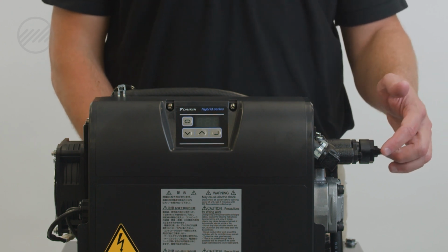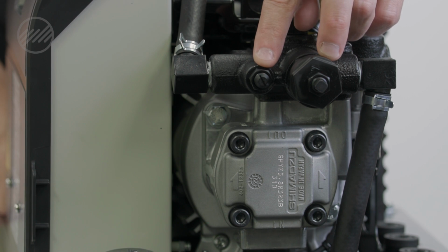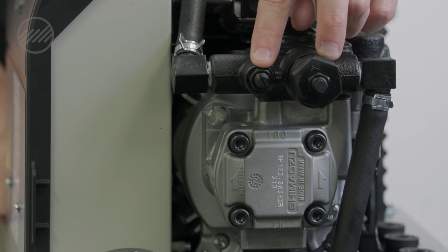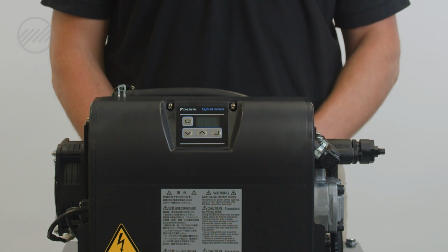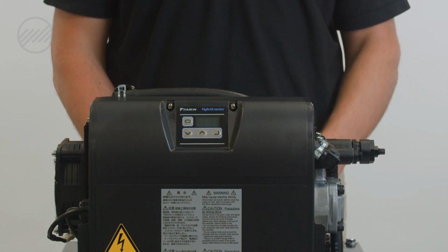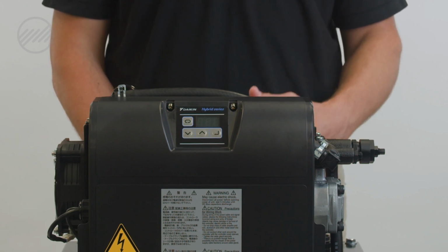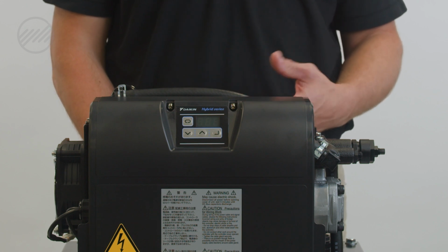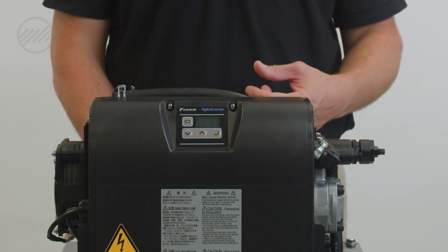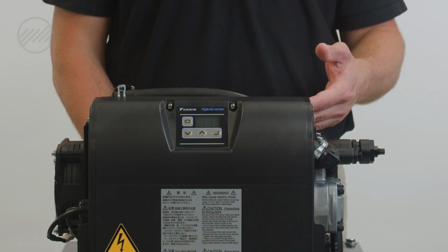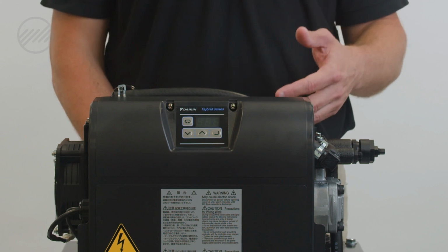Potentially, our motor RPM was not set correctly at installation, or there has been a change in your circuit, such as a leaking actuator or valve, that's allowing continuous flow of oil through the system. This will raise your motor RPM, ultimately generating more heat.